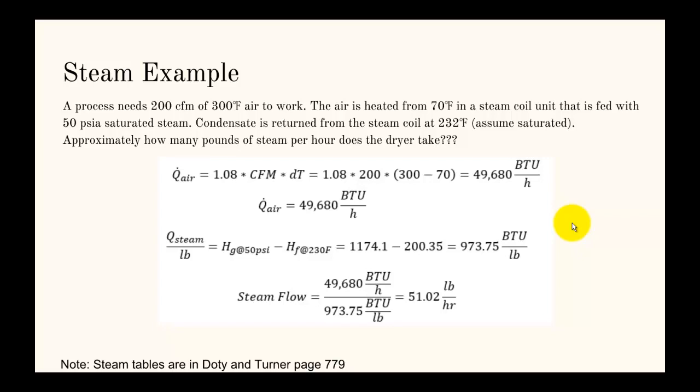Now let's go to a steam example. In this case, whenever you see steam, you want to go to the steam tables. They're in Doty and Turner on page 779. A process needs 200 CFM of 300 degree Fahrenheit air to work. The air is heated from 70 degrees in a steam coil that's fed with 50 psia saturated steam. The condensate is returned from the steam coil at 232 degrees Fahrenheit, and we're going to assume that condensate is saturated. We need to figure out how many pounds of steam per hour this dryer takes.